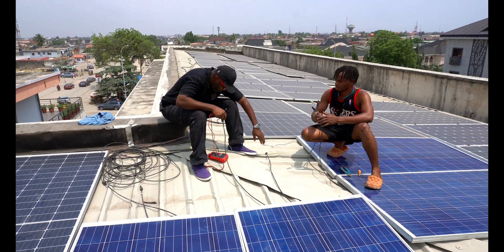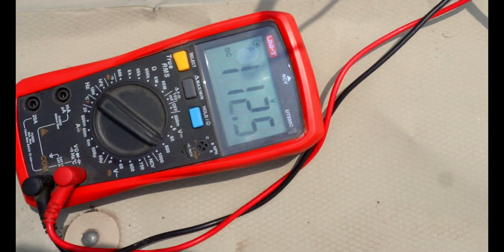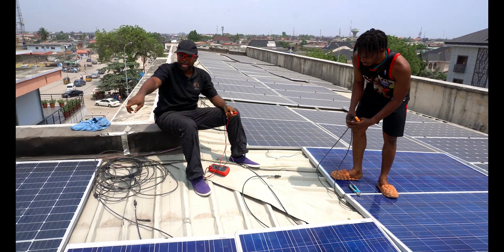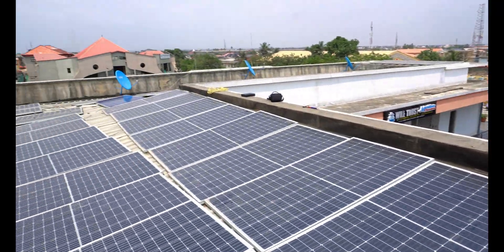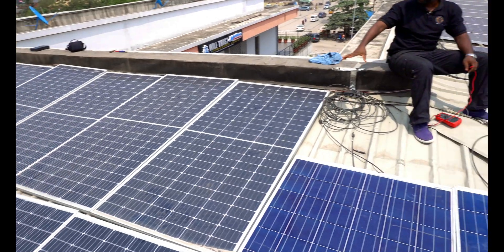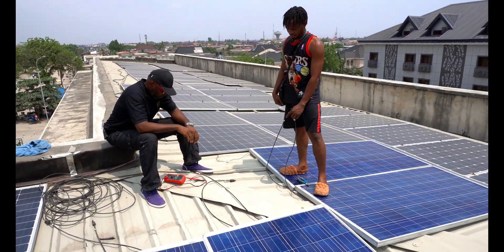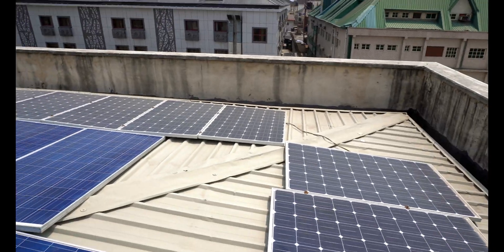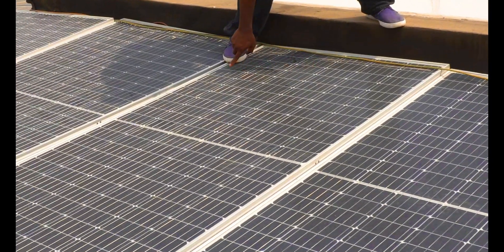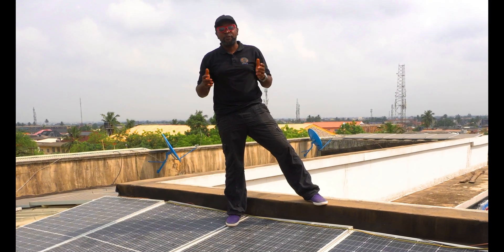Naturally, you will test to make sure the solar panels are all working. We want to add solar panels — we're adding those other ones over there. We're adding a whole lot, scattered all over the place, just to add more energy to what is already existing here. Because when you have dust on your solar panels like you do right now, it actually drops your output by as much as 40 percent.